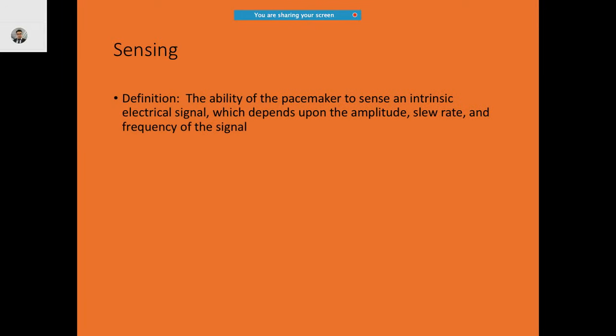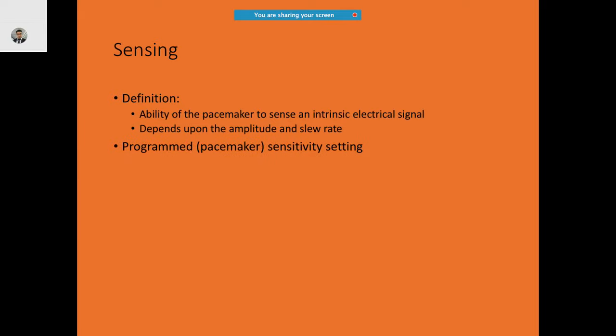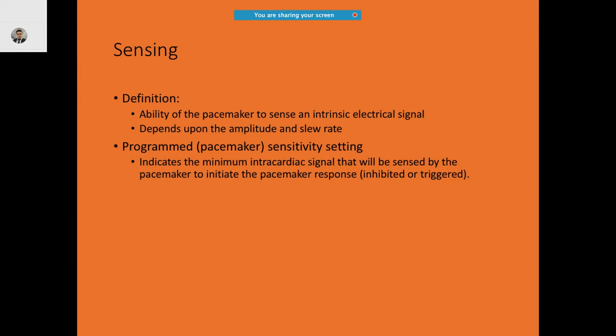In sensing, it is the ability of the pacemaker to sense an intrinsic electrical signal, which depends upon the amplitude, slew rate, and frequency of the signal. Programmed pacemaker sensitivity indicates the minimum intracardiac signal that will be sensed by the pacemaker to initiate the pacemaker response. There are intrinsic events coming from the patient — these are important when evaluating pacemaker function.